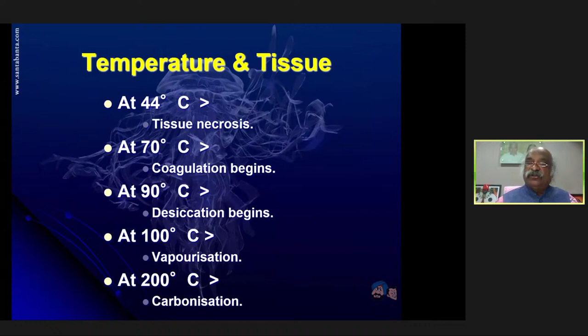Remember, we are not targeting carbonization. If you want vaporization, it must be a higher temperature. A little less is desiccation. Much less is coagulation. And tissue necrosis at 44 degrees is not visible macroscopically. Now there are some visible effects and some delayed effects on the tissues.